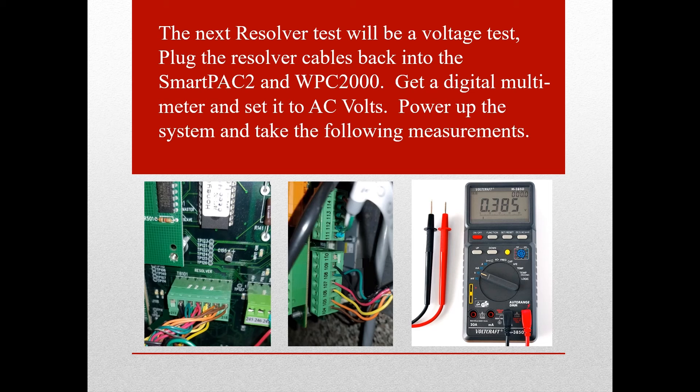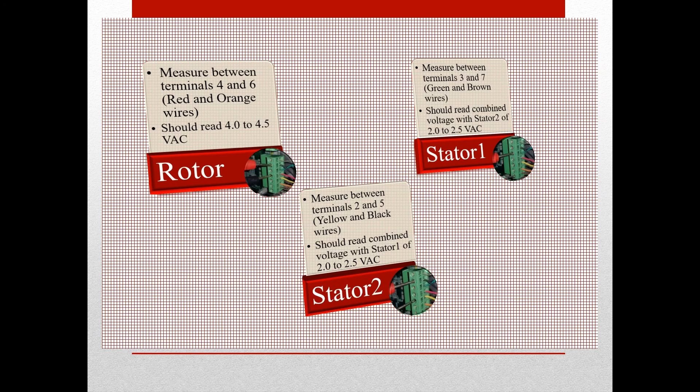The next resolver test will be a voltage test. Plug the resolver cables back into the SmartPAC 2 TB-101 and WPC-2000 TB-106. Get a digital multimeter and set it to AC volts. Power up the system and take the following measurements: measure the rotor on pins 4 to pin 6 — you should see approximately 4 to 4.5 volts AC. Stator 1 is measured on pins 3 to 7, and Stator 2 on pins 2 to 5. You should see a combined voltage between stators 1 and 2 of 2 to 2.5 volts AC. If these voltages are not as high as they should be but the resolver passed the ohms test, you likely have a processor board problem and should call tech support to troubleshoot further.